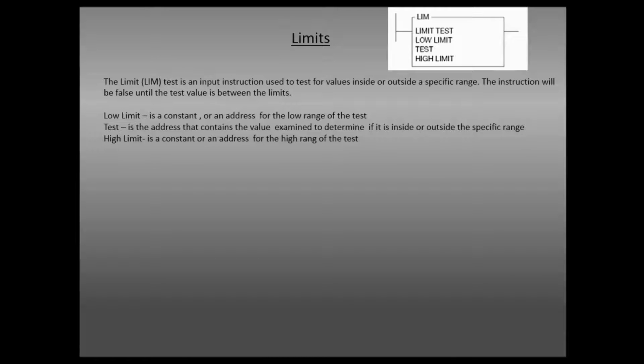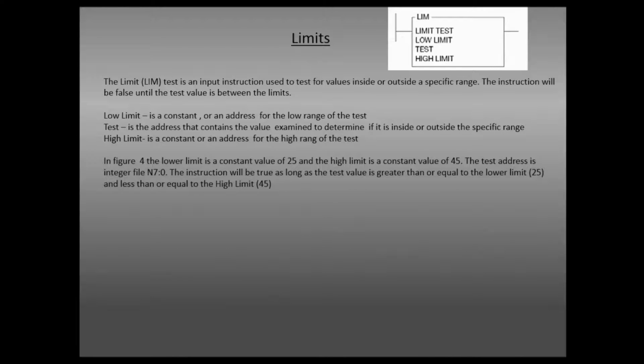Limits. The limit, LIM, test is an input instruction used to test for values inside or outside a specific range. The instruction will be false until the test value is between the two limits. Low limit is a constant or an address for a low range of the test. Test is the address that contains a value to be examined to determine if it is inside or outside a specific range. High limit is a constant or an address for a high range of the test.